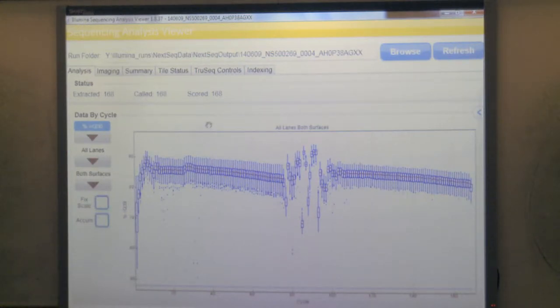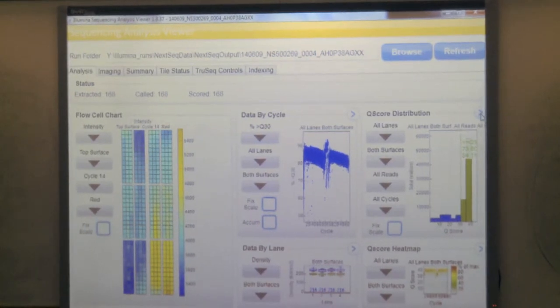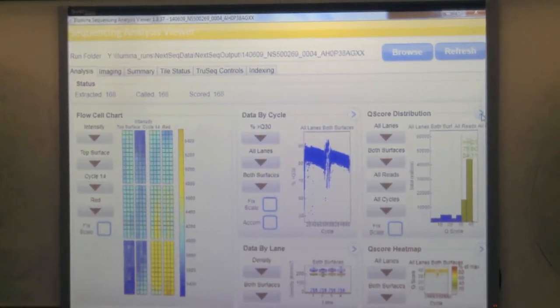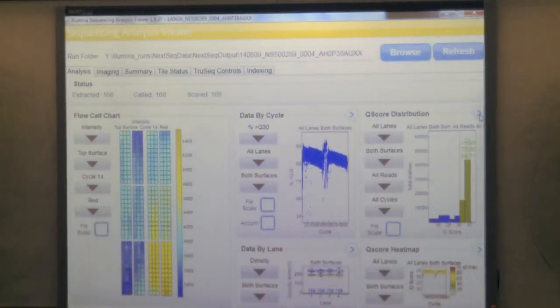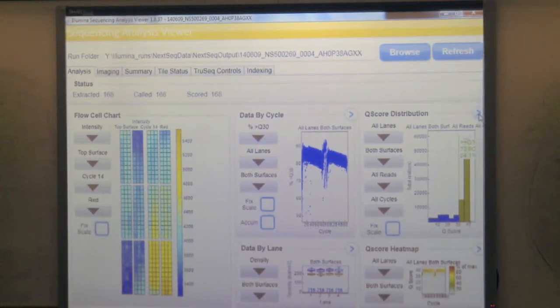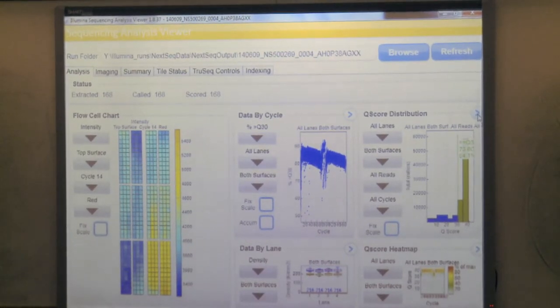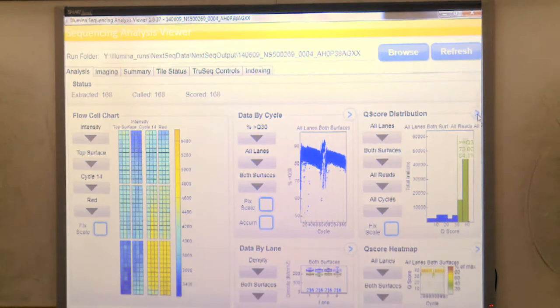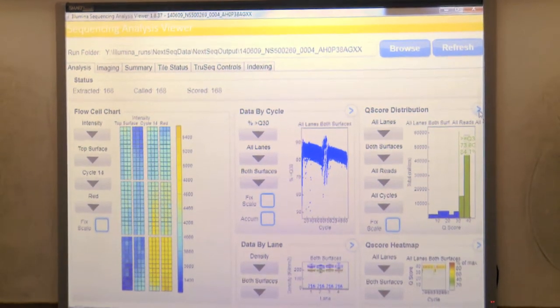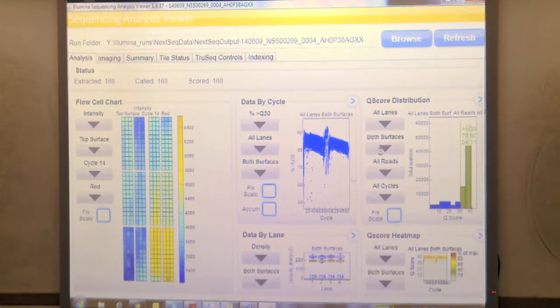I can pull out bad runs but maybe I shouldn't do that today. Do bad runs happen? Yes, of course - nothing is perfect. For these next three runs we've done so far, nothing looked bad; everything looks really, really nice. We had previously HiSeq runs that were not so great. It varies, and it's not necessarily an instrument problem - it can be a library prep problem or some other chemistry problem.